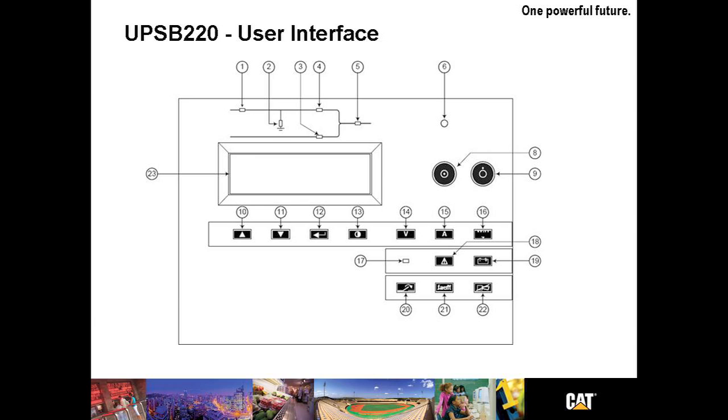Buttons eight and nine turn the inverter on and off, hence transferring the load to and from bypass. Items 10 and 11 allow you to scroll through the display, while number 12 allows you to select an item on the screen. Button 13 pages you through the list of menus. Numbers 14 and 15 allow you to choose if you are looking at volts or amps, while 16 allows you to look at watts and frequency. 18 and 19 are the alarm and battery key.